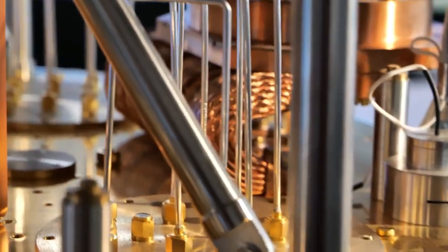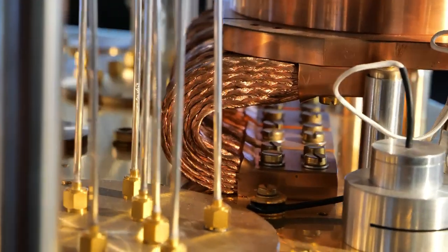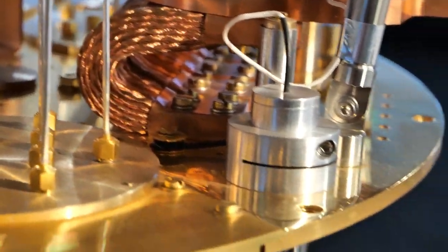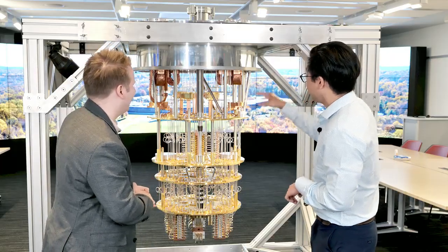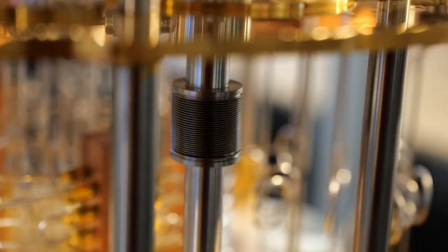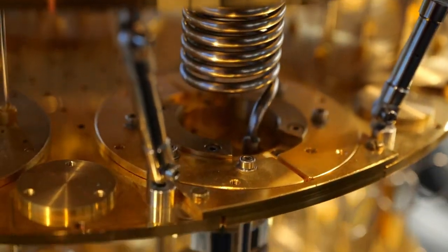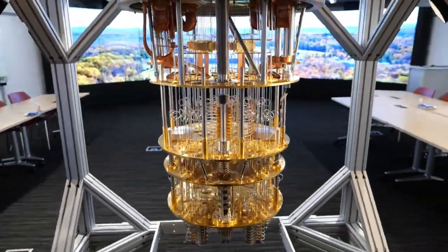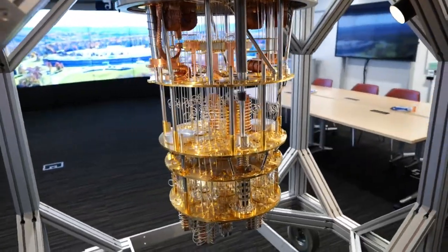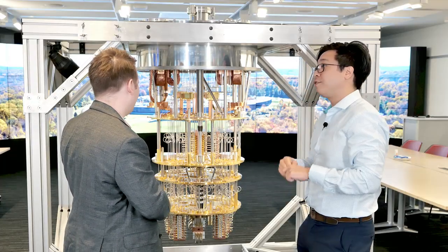When I first came in, before we started filming, I saw these massive copper wires, and I thought, oh, you must have some high-powered current in there. But you were like, no. Yeah, a lot of these are just for heat sinking to what we call cold heads. So you've got one that side, one this side. These are the systems with the pulse tube in them that have a closed system of helium, and that's what gets this plate that you're looking at here to 4 Kelvin.